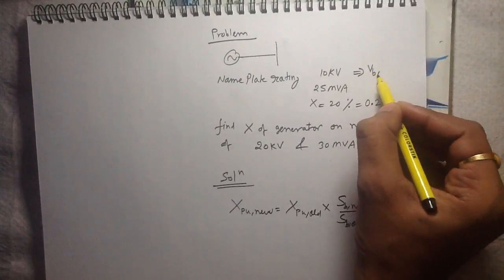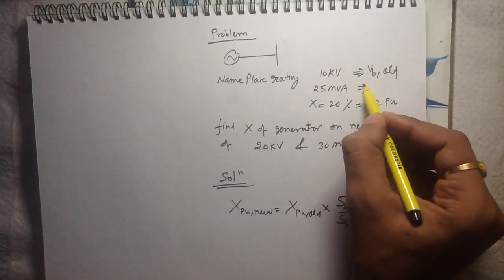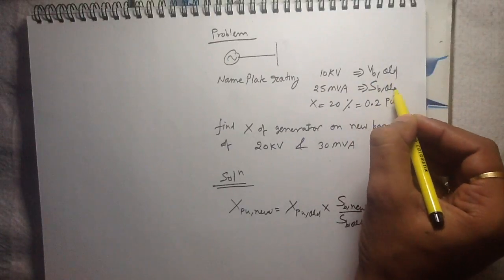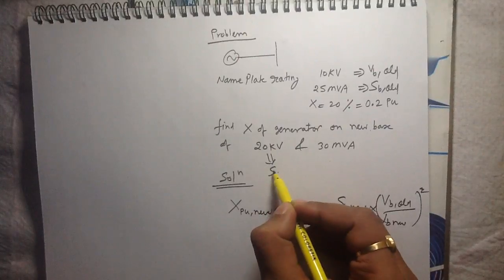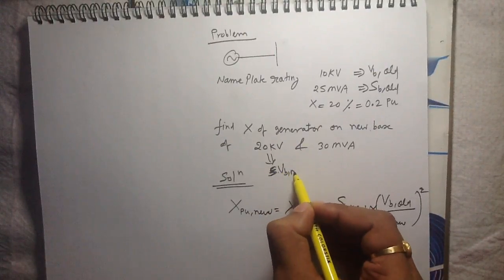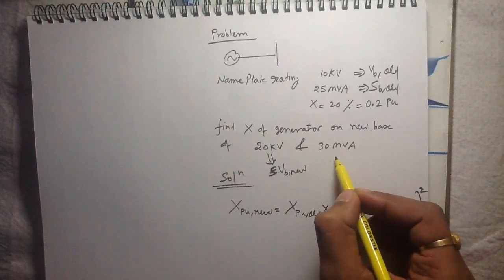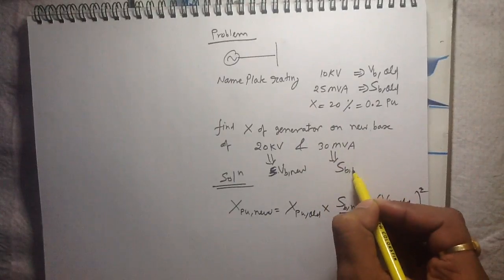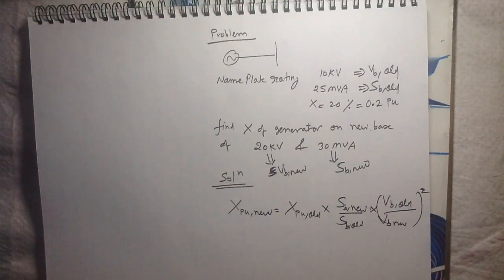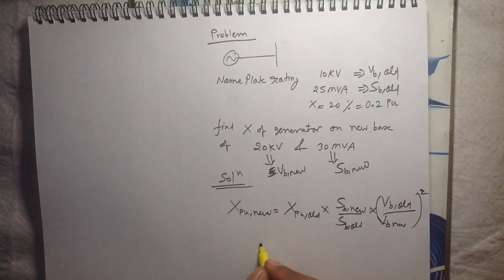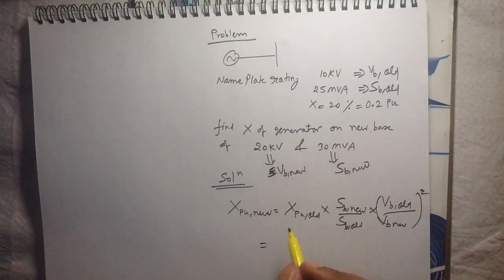This is the old base voltage and this is the old base power. On a new base voltage of 20kV and on a new base power of 30MVA, we have to find out the new per unit reactance. Put all these values in this formula.